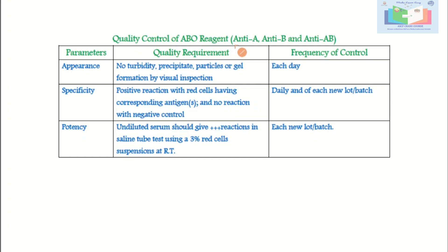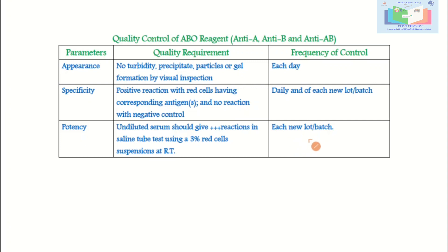Quality control of ABO reagents — Anti-A, Anti-B, and Anti-AB: for appearance, there should be no turbidity, precipitation, particles, or gel formation by visual inspection each day. For specificity, there should be a positive reaction with red cells having the corresponding antigens and no reaction with the negative control, done daily and with each new lot or batch verification. With A or B cells there should be a positive reaction, and with O cells (blood group O) there should be no reaction. For potency, test the undiluted serum — it must give at least a 3+ reaction in saline tube testing using a 3% red cell suspension at room temperature. This is done with each new lot or batch, commonly called lot-to-lot verification.